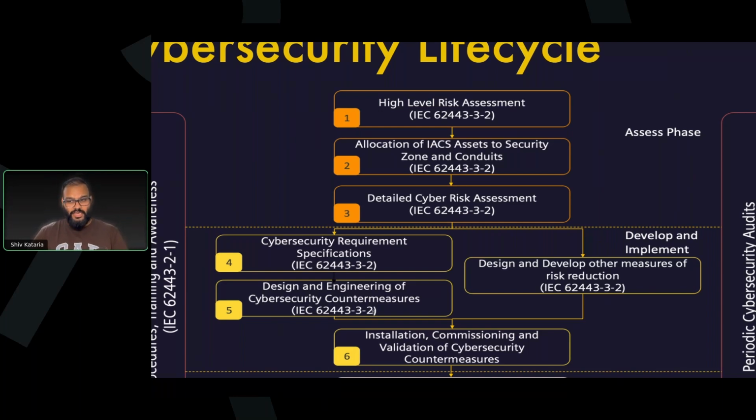Post the CRS, we design and engineer the security. Your outcome might say that you need to improve your access control mechanism. And then what would you design? You design a network that allows you to connect your devices through an Active Directory domain controller, as well as possibly RADIUS-based authentication for your IEDs, your RTUs, and your network infrastructure. That is what you are going to design. And then you will implement through installation, commissioning, and validation of the security.